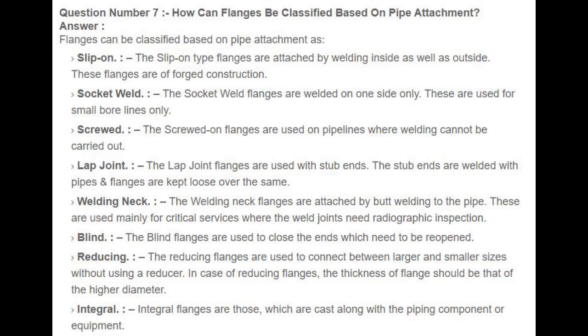Welding neck — attached by butt welding to the pipe, used mainly for critical services where weld joints need radiographic inspection. Blind — used to close the ends which need to be reopened. Reducing — used to connect between larger and smaller sizes without using a reducer; the thickness of the flange should be that of the higher diameter. Integral — those which are cast along with the piping component or equipment.